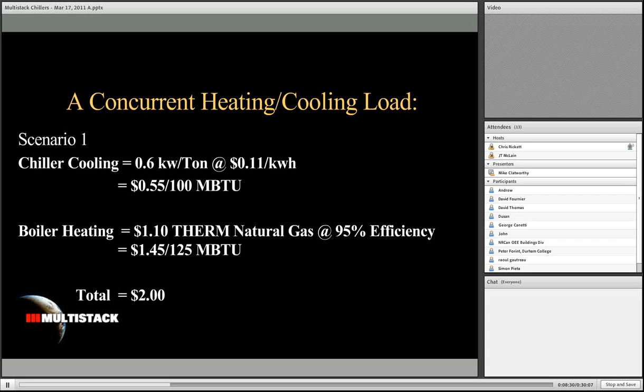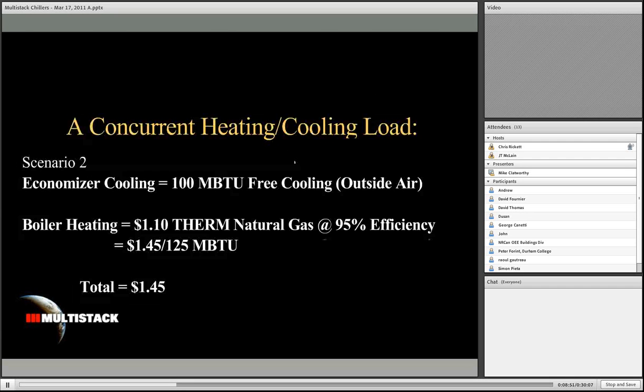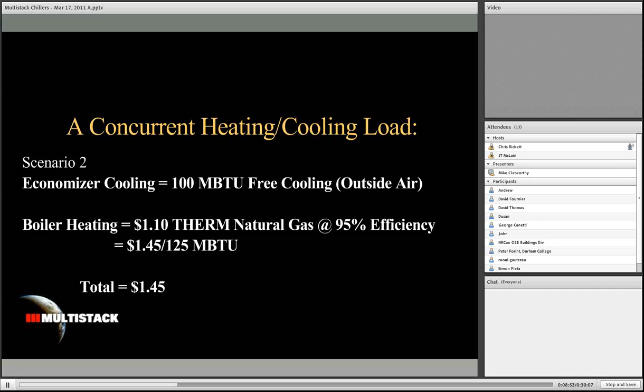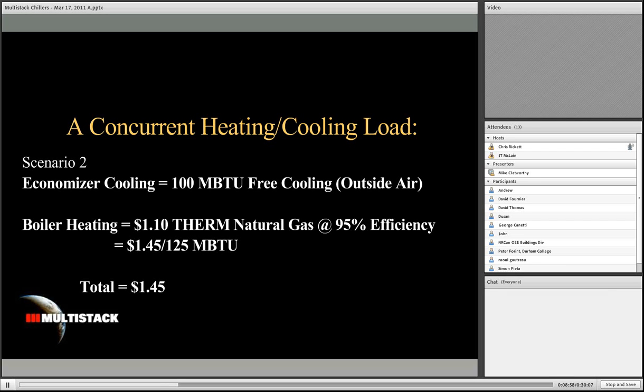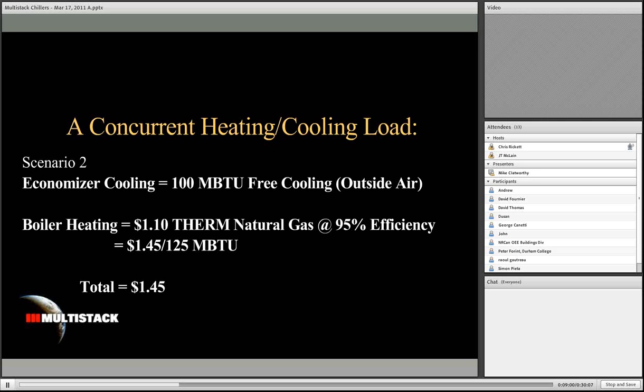So scenario one, the chiller would be running at 0.6 kW per ton, 11 cents per kilowatt hour blended rate. And so a therm of cooling would cost me 55 cents. Now, that's my cooling. What about the heating, the boiler heating? Well, at $1.10 per therm of natural gas with a 95% efficient boiler, that therm of heating is going to cost me $1.45, for a total cost of $2. So a therm of concurrent heating and cooling capacity in this scenario would be $2.